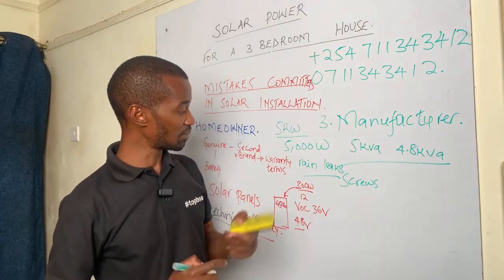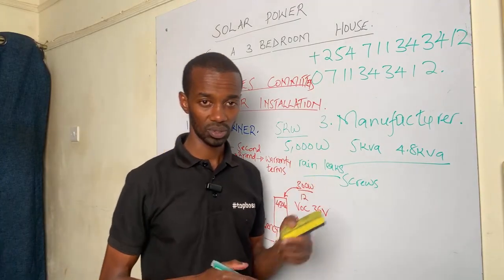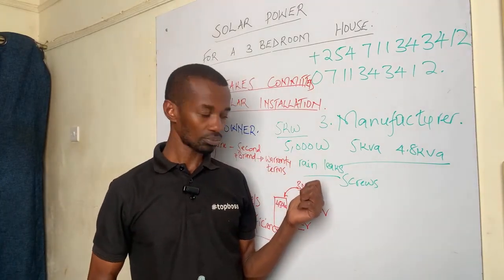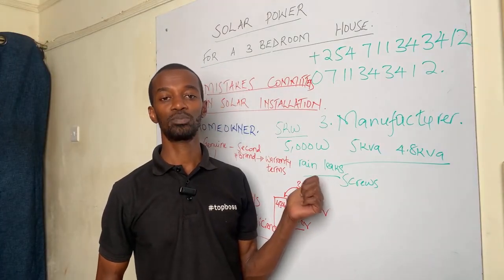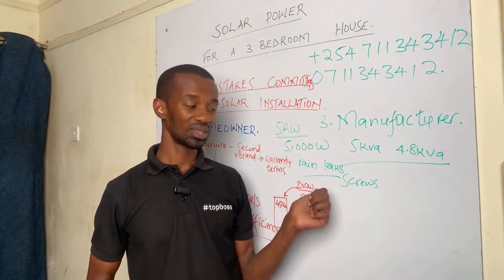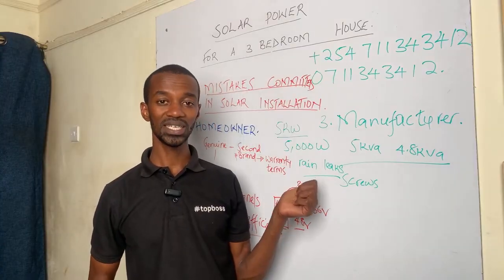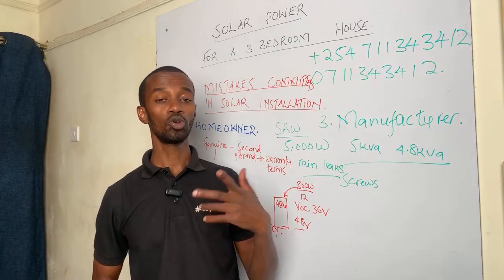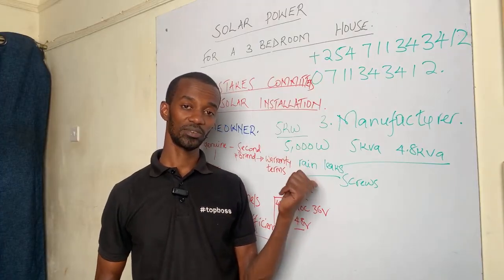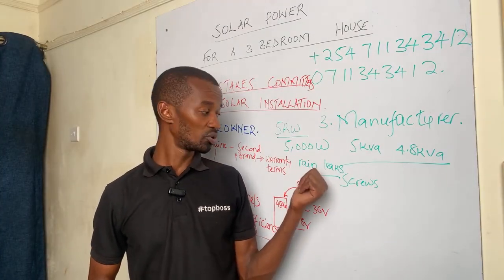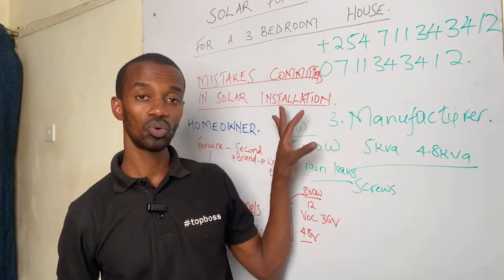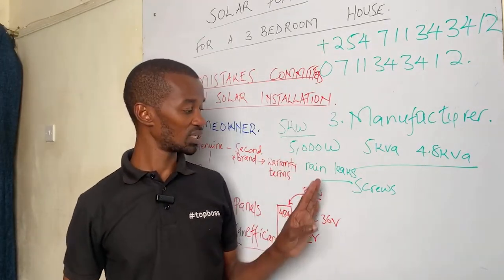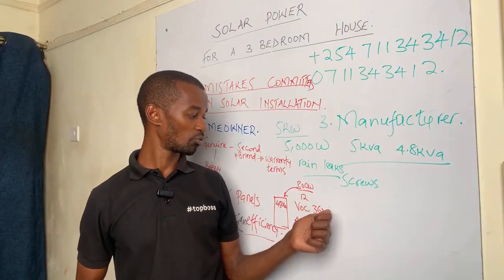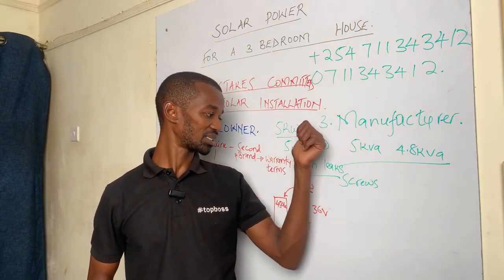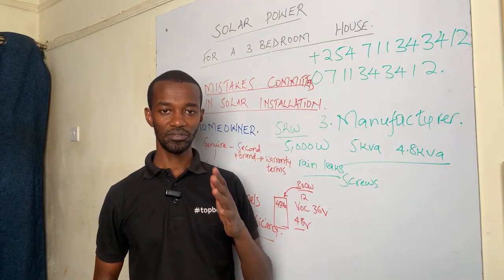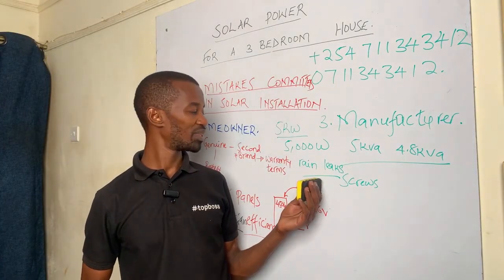This is another mistake people are not aware of. When that motherboard is ruined, in many cases you will not get that spare part, especially if the company phased out that product or is no longer manufacturing that specific inverter, meaning they're also not producing the parts. So you'll have to replace the entire inverter. The issue is, if that battery is not compatible with the new inverter, you'll be forced to replace both the battery and the inverter. So you must be very careful when it comes to the products that you buy.